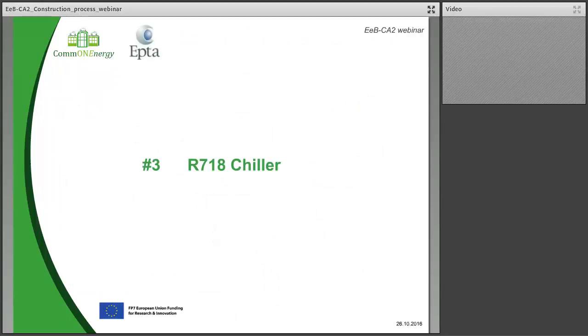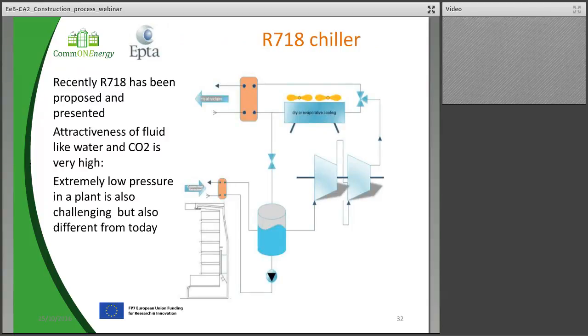Again I have to switch back, sorry, to this slide because the other diagram is not present. So if we would be able to add, in place of this equipment, this water loop based also on a compressor, we can keep this water down to 18 degrees, even when the ambient is very high, up to 45 degrees, and gain efficiency on the refrigeration side. And these small temperature differences between 18/20 and 45 can be the good work and the good job of a water chiller.